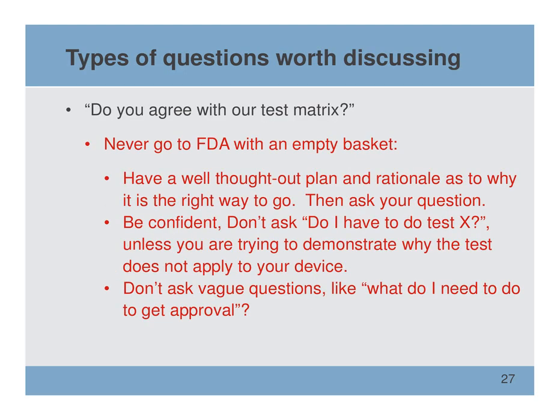So as far as types of questions, a little more detail about the kind of questions you want to ask. First of all, you should never go to the FDA with an empty basket. You should never say, what should I do? Make sure you have a well thought out plan, then ask the questions. So make sure you've got a case for what you're doing. Don't ask them, do I have to do this test? Say, look, we know there's a guidance out there that says we should do it, but we've decided we don't need to do it, and here's why.